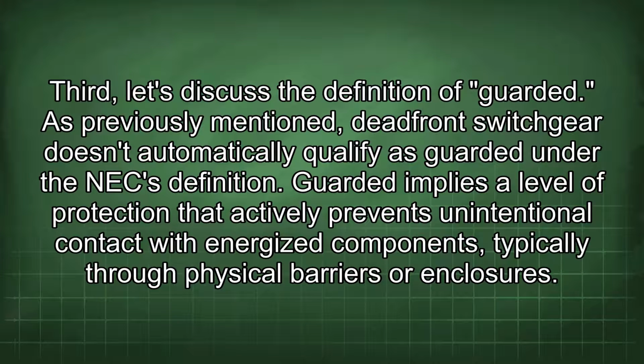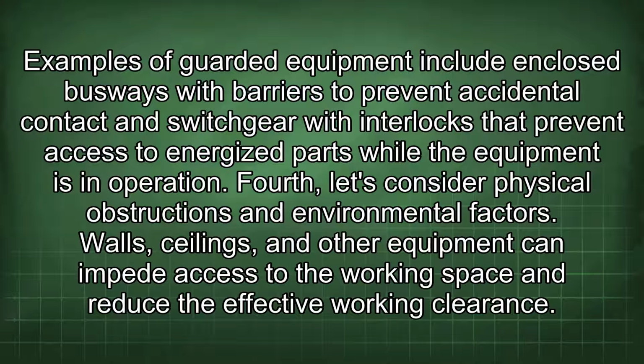Third, let's discuss the definition of guarded. As previously mentioned, Deadfront Switchgear doesn't automatically qualify as guarded under the NEC definition. Guarded implies a level of protection that actively prevents unintentional contact with energized components, typically through physical barriers or enclosures. Examples of guarded equipment include enclosed busways with barriers to prevent accidental contact and switchgear with interlocks that prevent access to energized parts while the equipment is in operation.